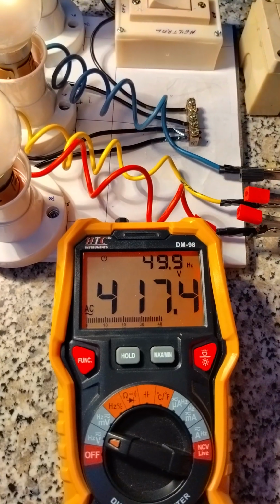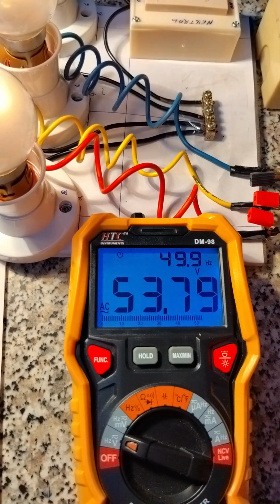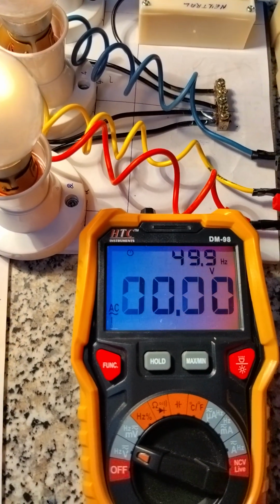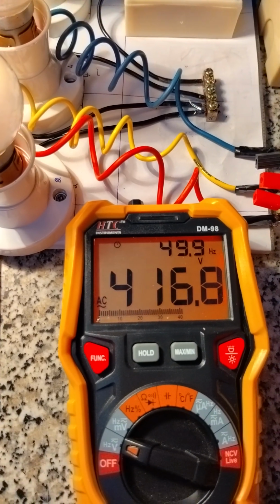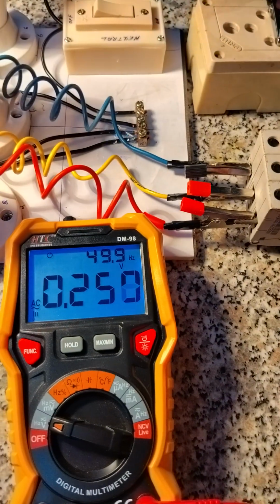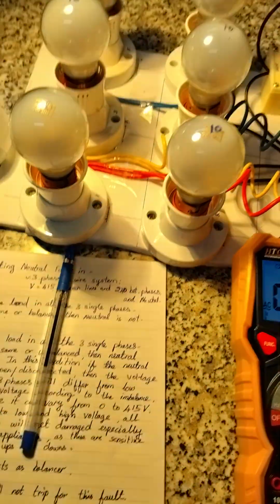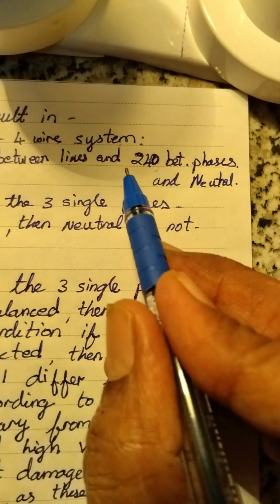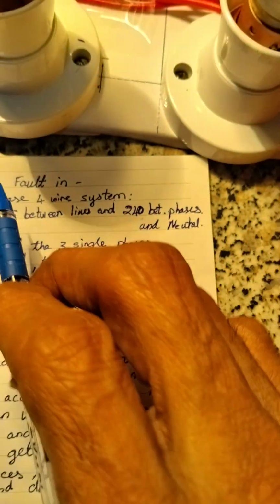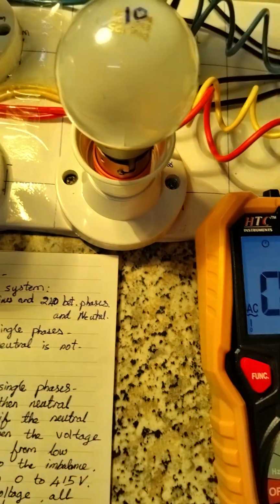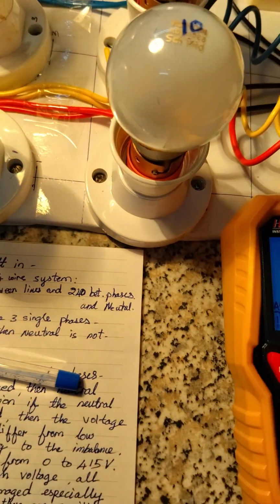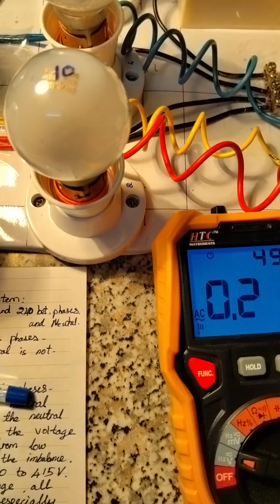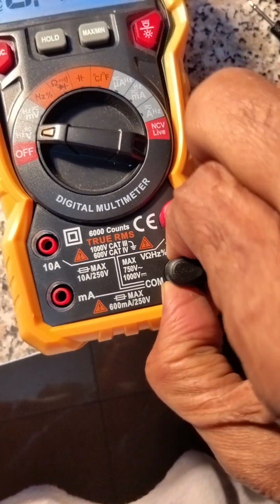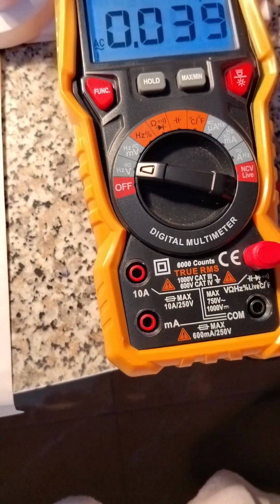RY, YB, then RB. Okay, now I will switch off. Now we have checked the voltage between lines. Now between each phase and neutral we will check the voltage. It may not be 240, it may vary by 10 volts like that. Now what I have to do is, I have to remove this probe. For convenience, I have to remove this probe.